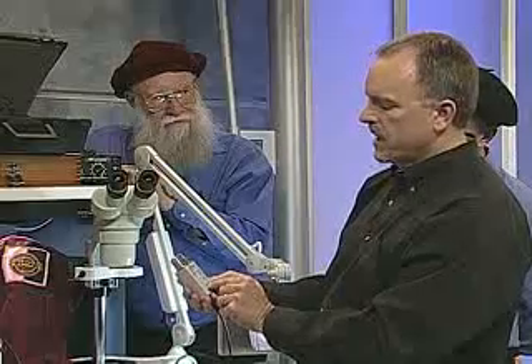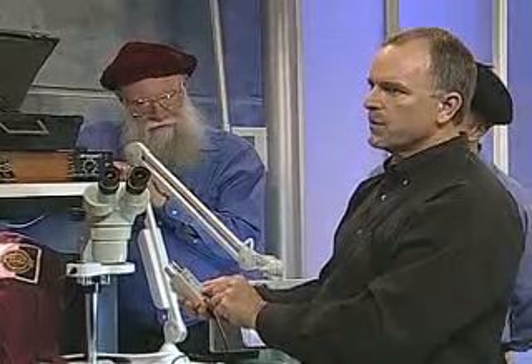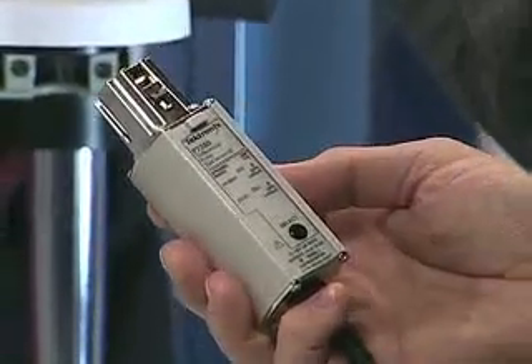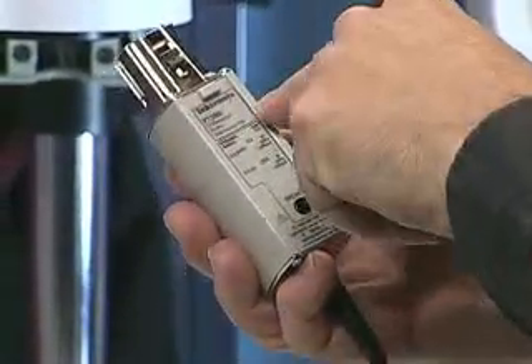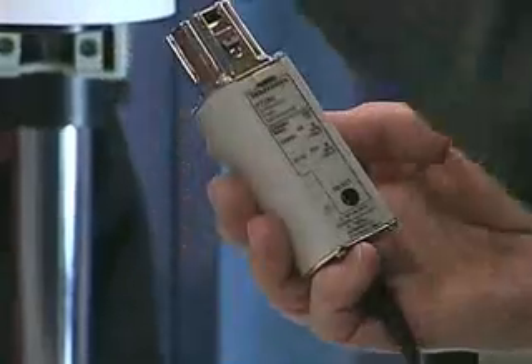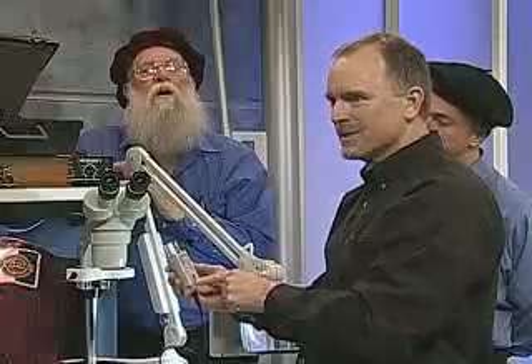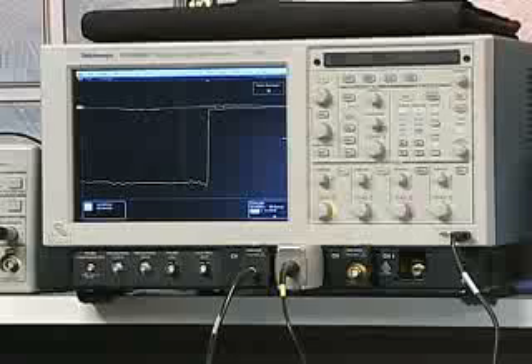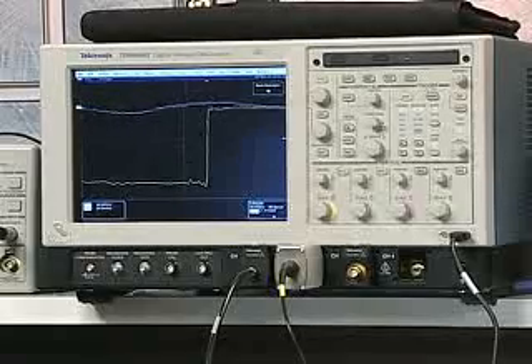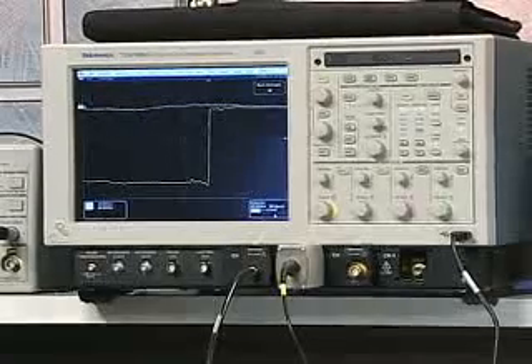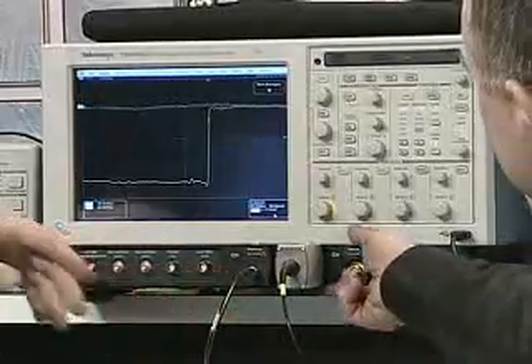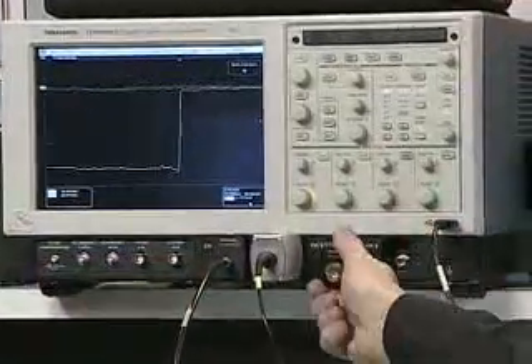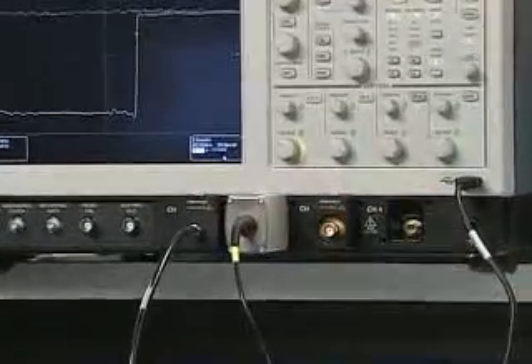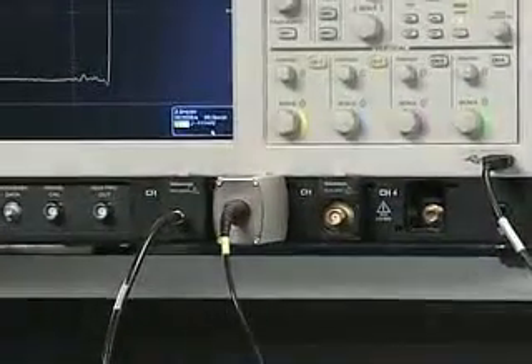And there are things like range settings. This one has a range button that will select attenuation, so if you have a really small signal swing, a few millivolts, you can set this in a very sensitive setting, but it's actually the scope changing settings in the probe, even though the button's on the probe. So a lot of interaction and intelligent system calibration between the two devices. And if you do want a conventional BNC or SMA, you just pop this little adapter in and off you go. Whichever type you need, we have adapters, even for other connector types. So whatever you need to bring in 50 ohms, you're covered.